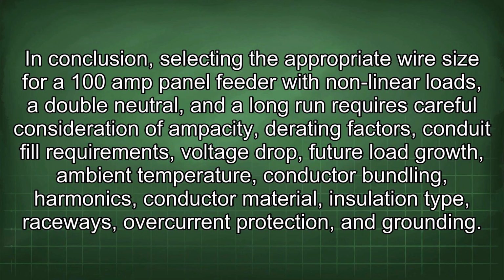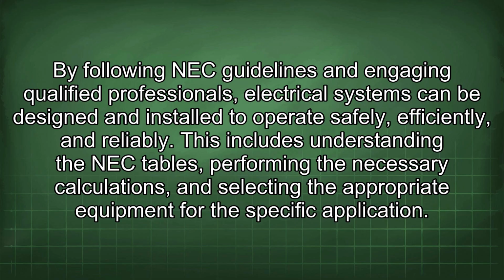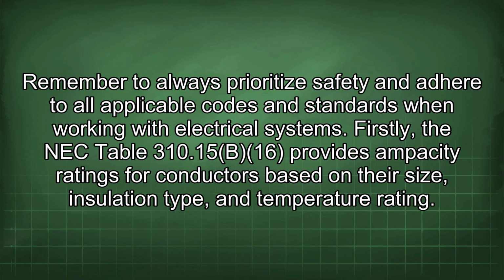In conclusion, selecting the appropriate wire size for a 100 amp panel feeder with nonlinear loads, a double neutral, and a long run requires careful consideration of ampacity, derating factors, conduit fill requirements, voltage drop, future load growth, ambient temperature, conductor bundling, harmonics, conductor material, insulation type, raceways, overcurrent protection, and grounding. By following NEC guidelines and engaging qualified professionals, electrical systems can be designed and installed to operate safely, efficiently, and reliably. This includes understanding the NEC tables, performing the necessary calculations, and selecting the appropriate equipment for the specific application. Remember to always prioritize safety and adhere to all applicable codes and standards when working with electrical systems.